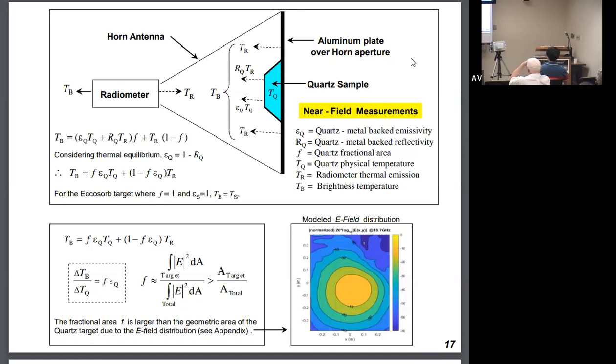So the question is, what happens if the emissivity is not 1? Does this still hold? Here is what you do. You get this equation again, and if you take the slope, the change in brightness temperature divided by the change in the temperature of the quartz, out comes this thing called fractional area times the emissivity. The question is, what is the fractional area? You would think it would just be the physical area of the quartz, or whatever surface, divided by the total area. That turns out not to be true. In fact, it depends on the electromagnetic field that this antenna sees from the target, divided by the field it sees over the complete area. And that happens to be greater than the physical area.